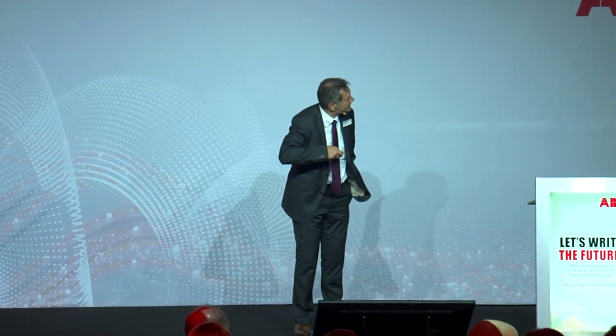This is an example of a sensor for gas-insulated switchgear, and this is an example of a current sensor, an optical current sensor for air-insulated switchgear. Here you see two pieces of electronics directly at the sensor. And directly at the sensor, this electronics is converting the analog signal, the low voltage analog signal, to a digital signal. High precision, very high speed, 4 kilohertz.